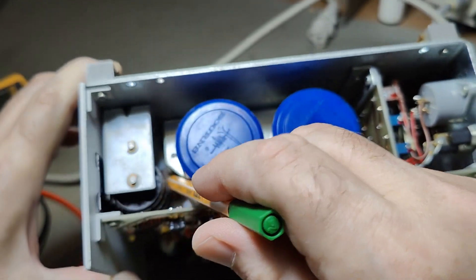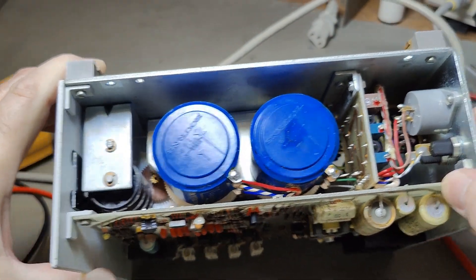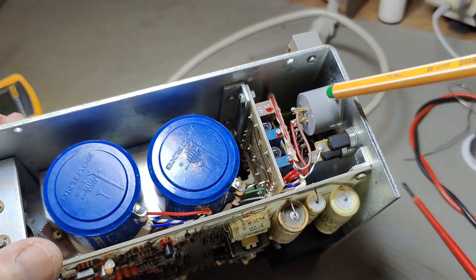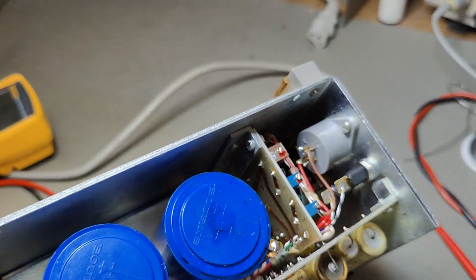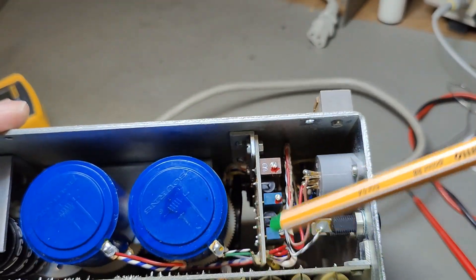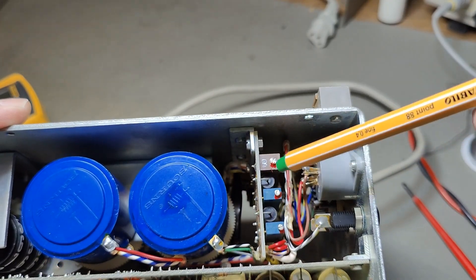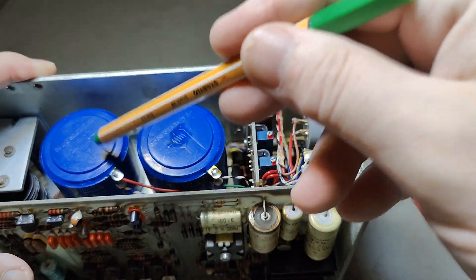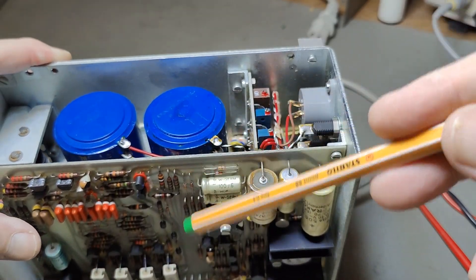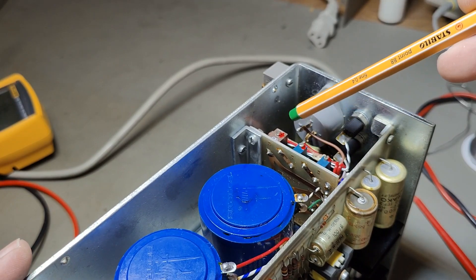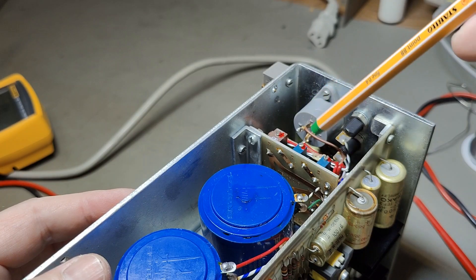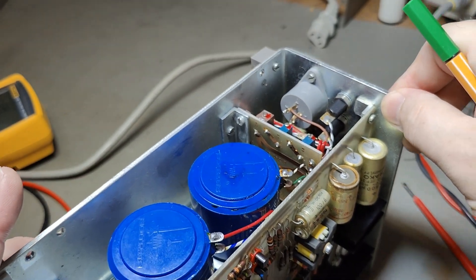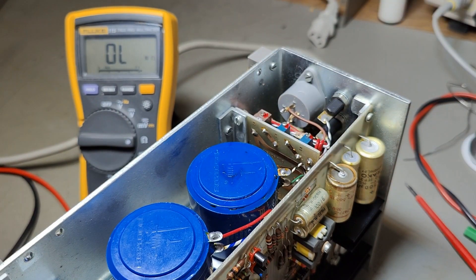That will be the motor shaft going to the readout. And then that is the connector for the sensor. And I see four pins, but two and two are connected together. And then we've got some high precision resistors connected to that and some trimmers that goes to the feedback system. And then another measurement reference signal that figures out if you're over or under. So all we have to do is measure the resistance in this bridge because this is the missing resistor in the bridge. So by measuring this, we could probably get a very good idea of what kind of sensor it is that we need.